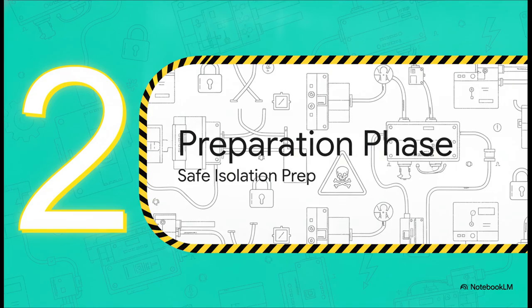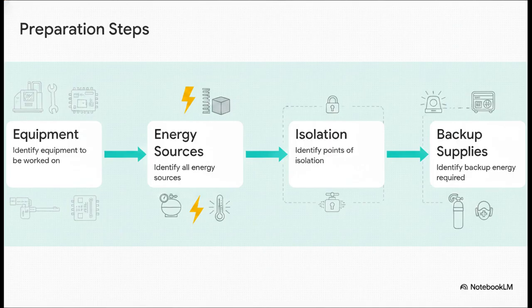All right. Section 2. Preparing for safe isolation. Listen, preparation is everything here. Step 1 is positively identifying the specific equipment you're working on, plus anything nearby that might present a risk. Step 2, spotting all the energy sources. And honestly, here's a curveball. It's not just electricity. You've got to look out for non-electrical energy too. Is there hydraulic or pneumatic pressure in a tank nearby? Is there mechanical energy, like the massive tension of a spring? What about stored heat in gear that's been running all day? Step 3 is finding all the actual isolation points for these hazards. And step 4 is figuring out if any backup supplies, like emergency lighting or medical oxygen, need to be kept running while you work.